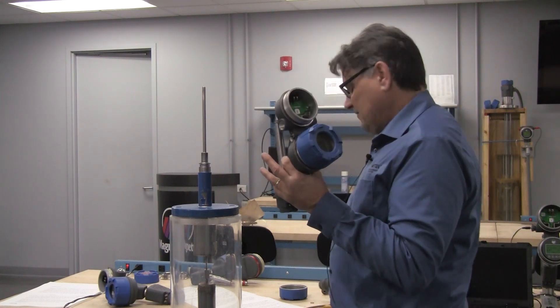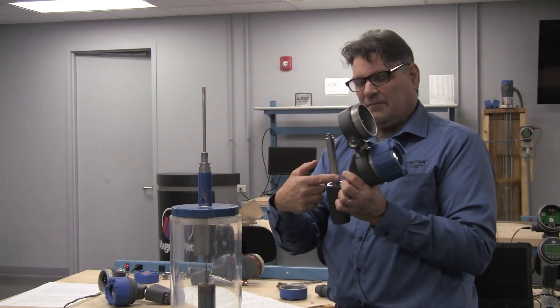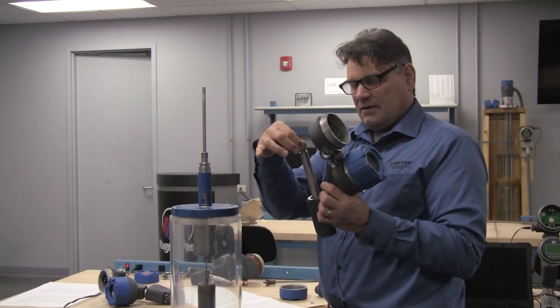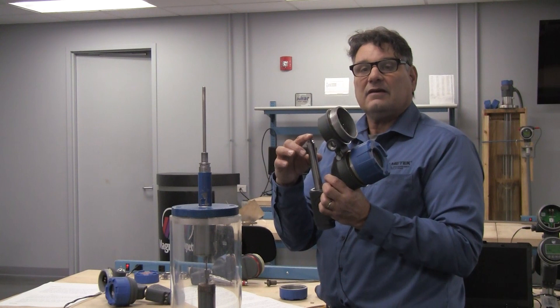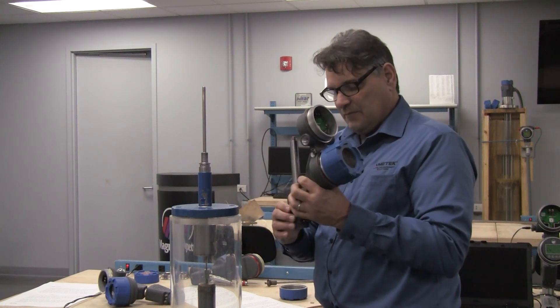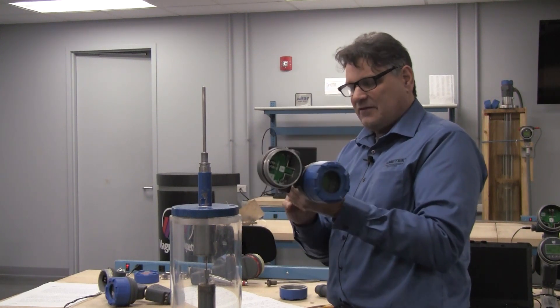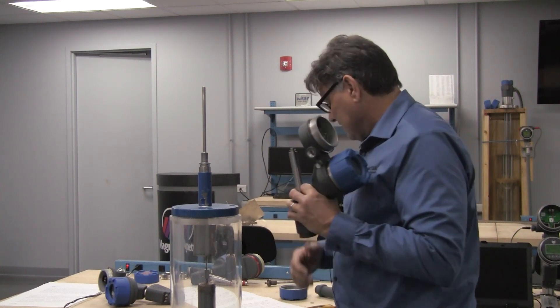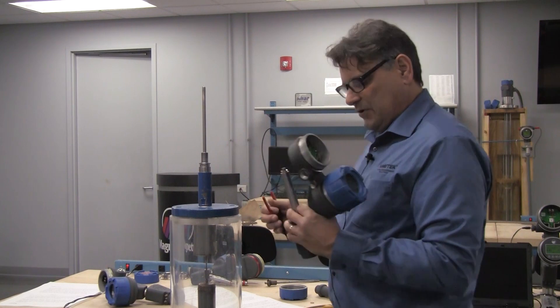And you'll see inside, you have the LVDT, the snap ring and the little washer, and then up through the center of the LVDT is the dummy enclosing tube. So we're going to need to pull that dummy enclosing tube out, that's there, so that when this is shipped, everything is held in place and it doesn't get damaged.